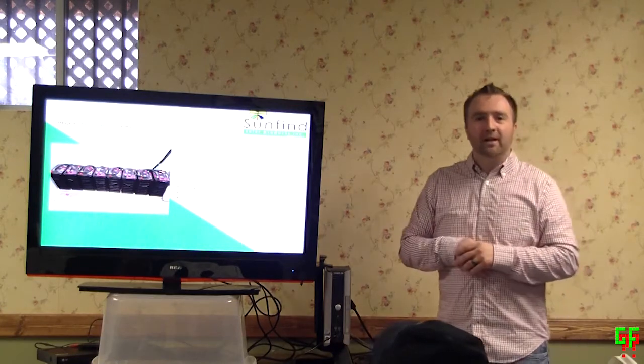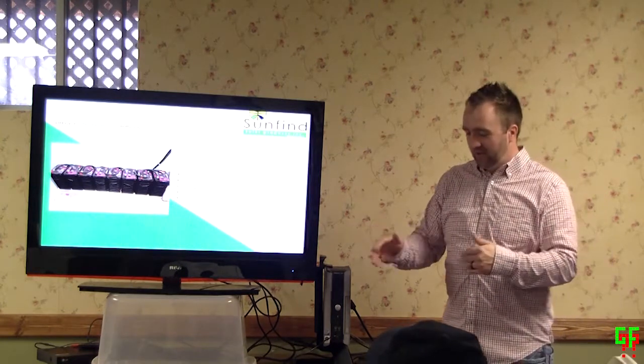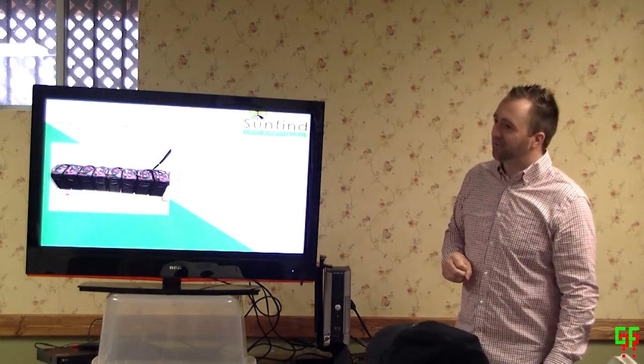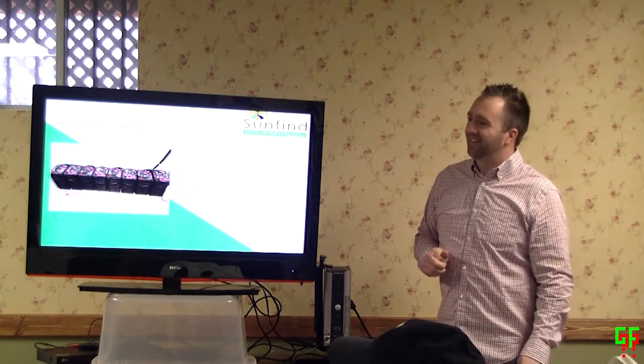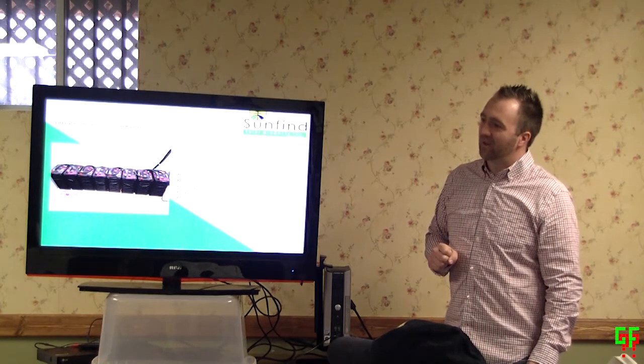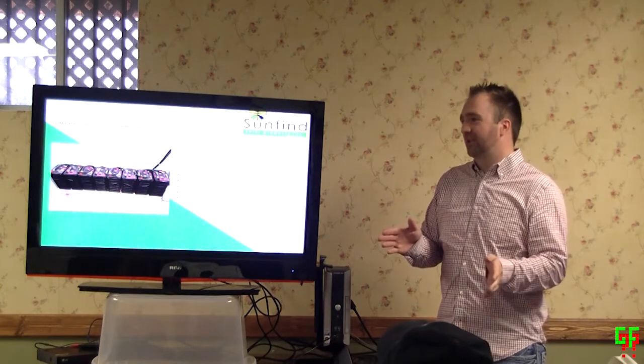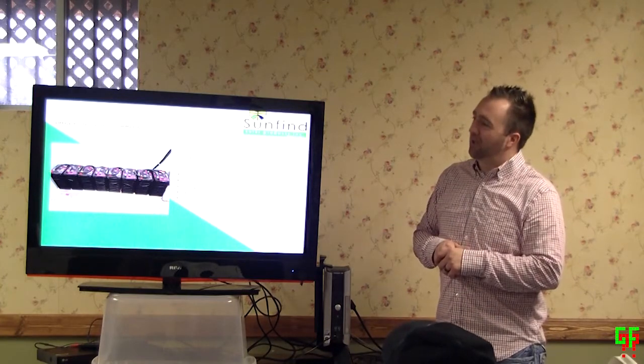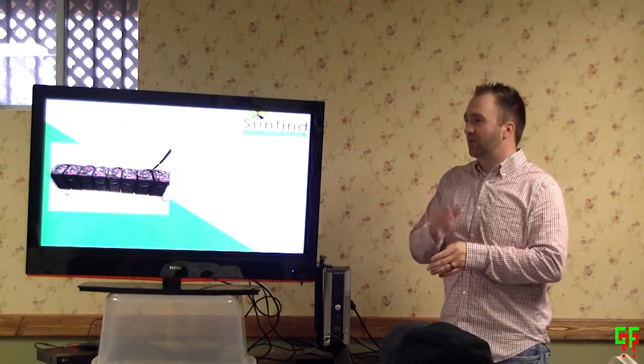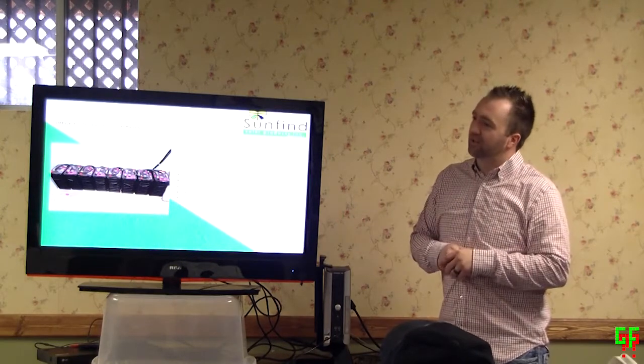Those batteries are about 16 inches high, 8 inches wide, and about 12 inches deep — they're about 115 pounds each, so heavy enough as it is. A battery cycle would be considered when you take enough energy out to go from full to dead. Most people use about 35 to 40% of the battery bank every day, so over about three days that would be a full cycle.